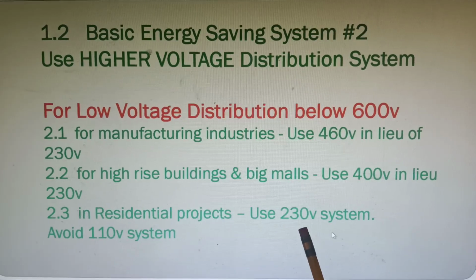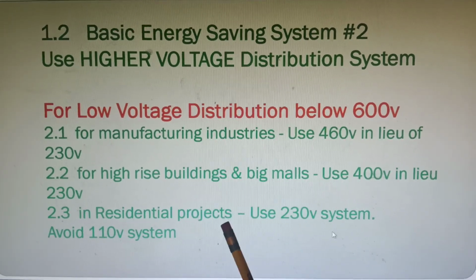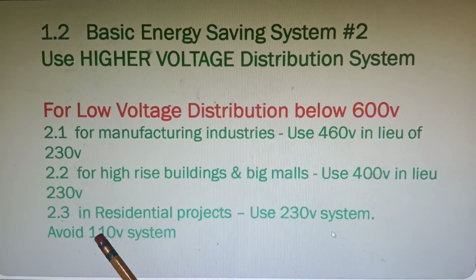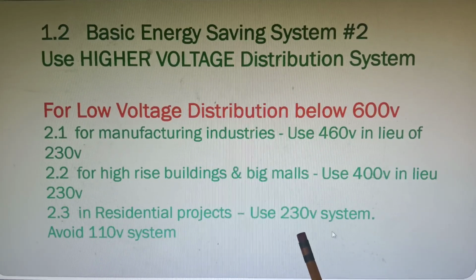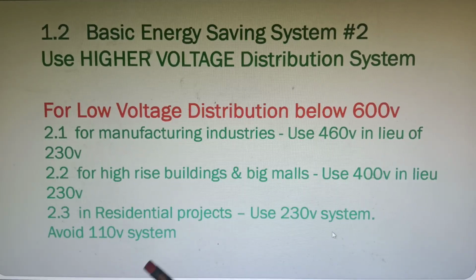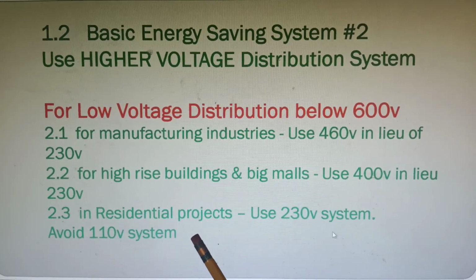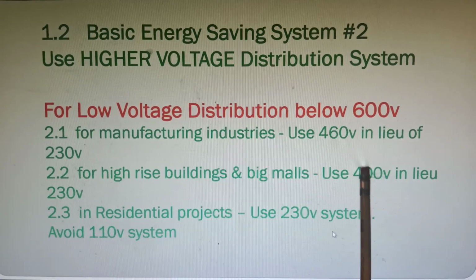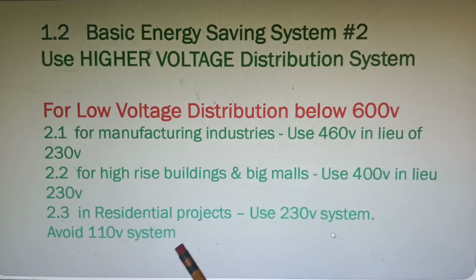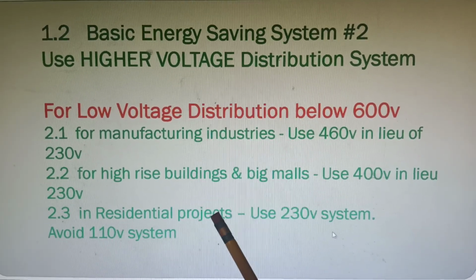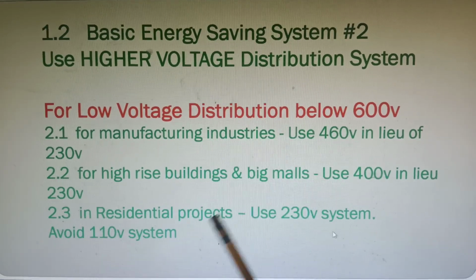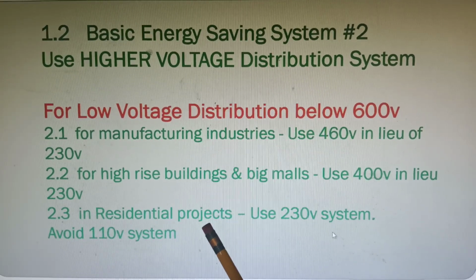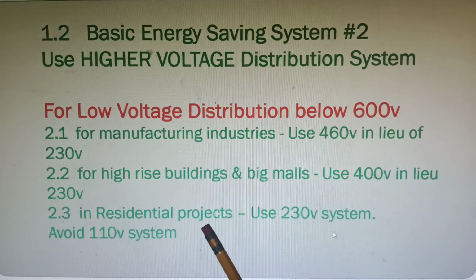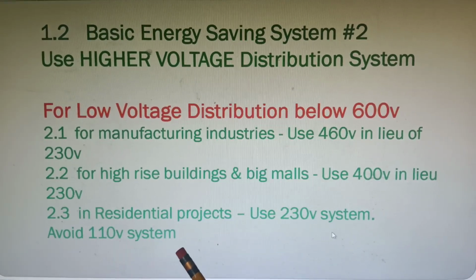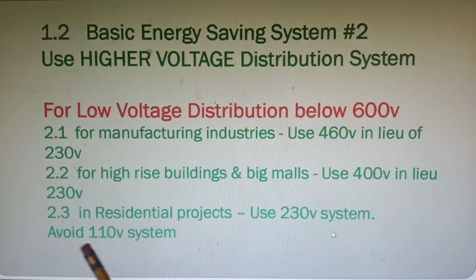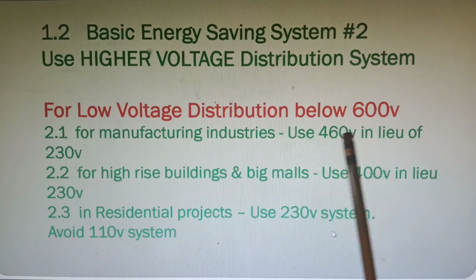as those if you use a 230 volt system. So again, not only will you have a larger size of wire when you use this as against this, but also, when you use a lower voltage system, since the currents will be very much higher than in a higher voltage system, it also follows that your efficiency, the losses, the square of the current times the resistance of the circuits, I squared R, the copper losses, wiring losses, circuit losses, will be much bigger in the lower voltages here. In the 460, very much smaller.